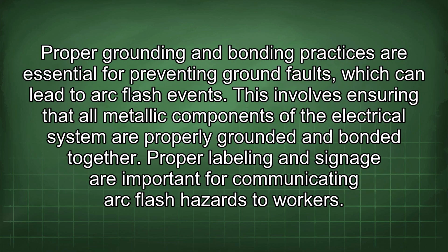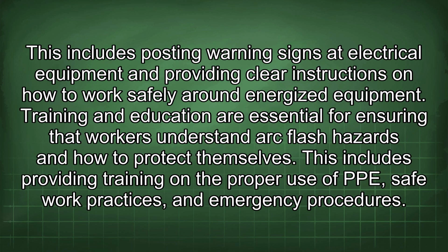Proper grounding and bonding practices are essential for preventing ground faults, which can lead to arc flash events. This involves ensuring that all metallic components of the electrical system are properly grounded and bonded together. Proper labeling and signage are important for communicating arc flash hazards to workers. This includes posting warning signs at electrical equipment and providing clear instructions on how to work safely around energized equipment.